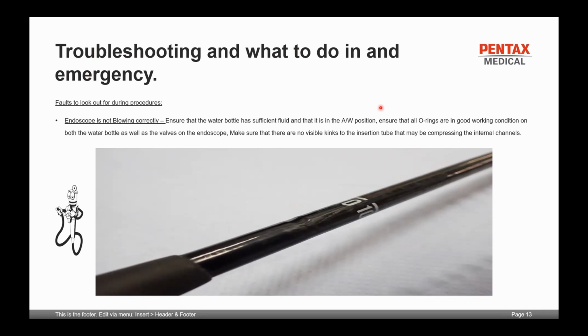And if you've got a faulty O-ring on the air-water valve or on the suction valve, what happens is the endoscopist insufflates inside the patient, and due to a faulty suction valve, the air that's being insufflated into the patient automatically gets sucked up through the endoscope. And then it doesn't inflate the bowel for him to be able to progress the endoscope during the case. So O-rings are quite an important part of checking, on the water bottle as well as the valves.